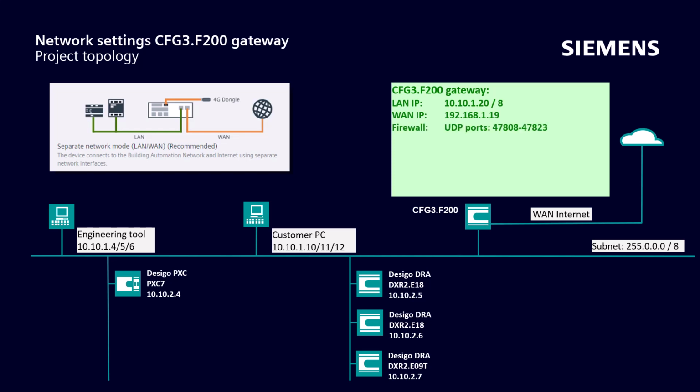In the firewall we have to enable both the required UDP and the TCP ports. For BACnet communication, we can select a single UDP port or, as we show here, activate an entire range. For the TCP ports we have to enter the two internal ports which are responsible for the communication with the Desigo Optic web client. The port 8090 is used for the secure HTTPS internet connection, and the port 8085 for the unsecure HTTP communication. In case the gateway needs to be set up for Modbus or KNX system communication, also the TCP port 502 or 3671 needs to be added in the list.